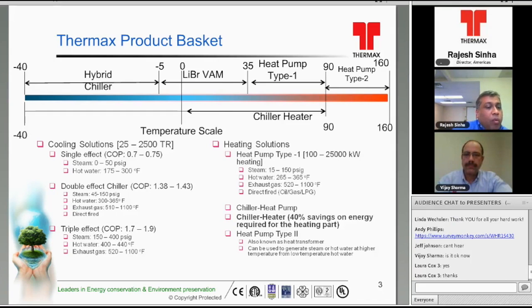Likewise, when you go with the double effect absorber, your energy consumption cuts down to half. Responding to the question which was already posed by Neil, the price for the double effect absorber would be roughly 25% more than a single effect absorber. So you have half the energy consumption, heat consumption per ton of refrigeration, and you have about 25% more investment necessary for a two-stage absorber over a single-stage absorber.